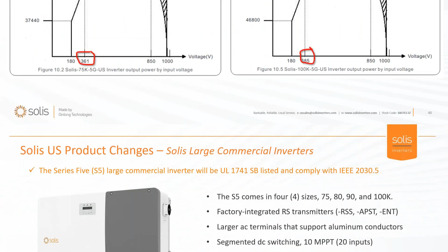Because not only can this inverter be very flexible when it comes to DC input, it's also got flexibility on the AC side. You can actually adjust the AC connection from 304 volts up to the standard 480, where it will put out full power. Now, if you connect this up to a transformer that's operating at 320 volts, it's not going to put out the full power that it's rated for. But you do have an inverter now that's got all those capabilities, is optimizing the performance of those old PV modules and really squeezing out all the investment out of that old legacy site.